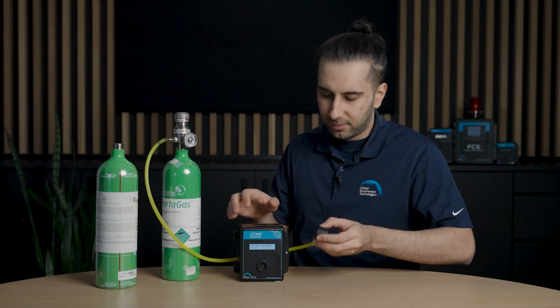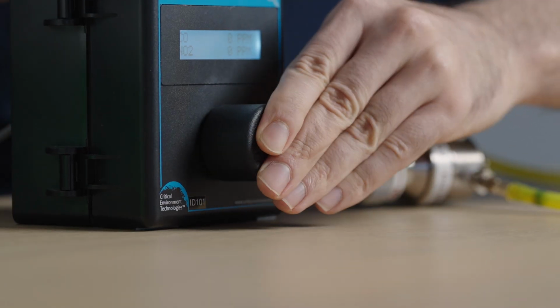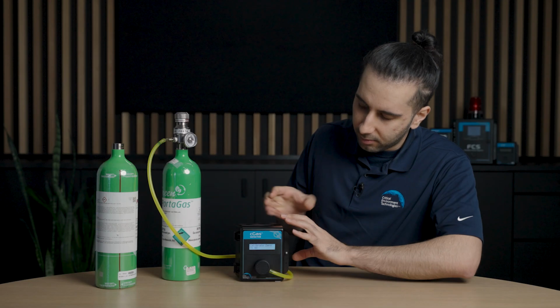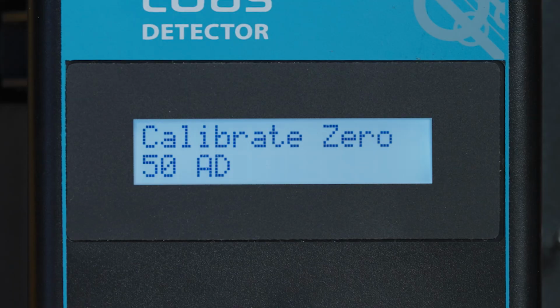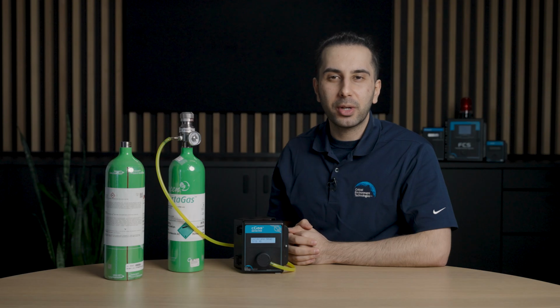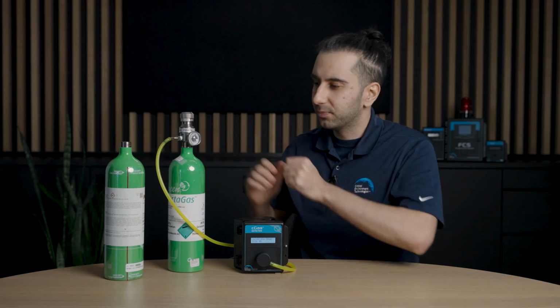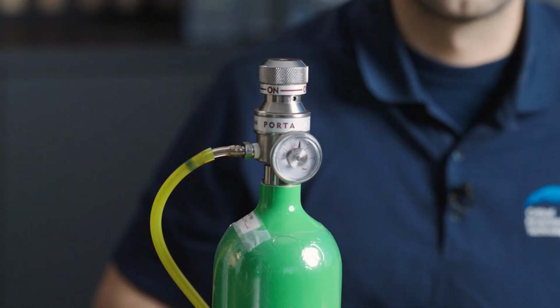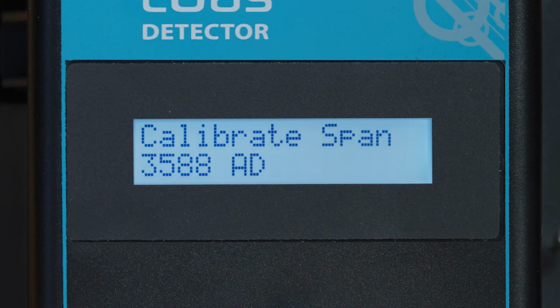Connect the calibration span gas cylinder to the detector. Press Enter and navigate to Calibrate Span. Now open the valve on the regulator to allow the span gas to flow for a few seconds. Then press Enter to start.